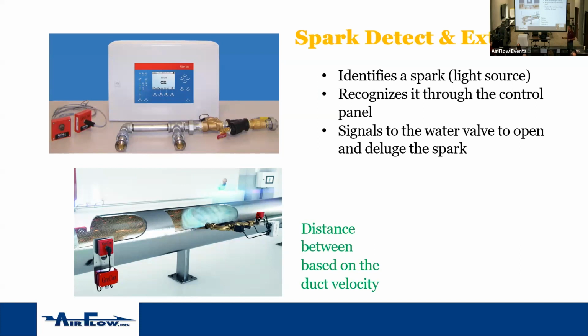One thing to note on this is this water is usually a non-potable connection somewhere in the system. It is not connected to your fire suppression system, because this could go off 6, 8, 10, 12, 14 times a day. And every time this goes off, it's going to start the flow of water. If you're connected to your fire suppression, you're going to get an alarm every time it goes off. So keep that separate from your suppression.